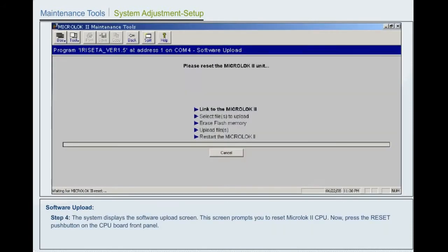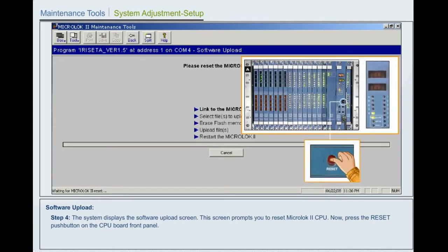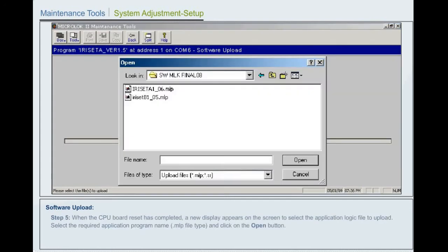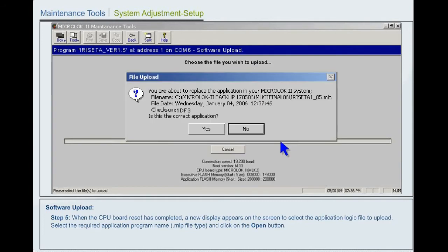Step 4. The system displays the Software Upload screen. This screen prompts you to reset Microlok II Central Processing Unit. Now, press the Reset Push button on the Central Processing Unit Board front panel. Step 5. When the Central Processing Unit Board reset has completed, a new display appears on the screen to select the application logic file to upload. Select the required application program name, Microlok programming file type, and click on the Open button.